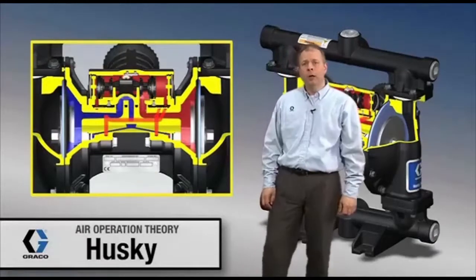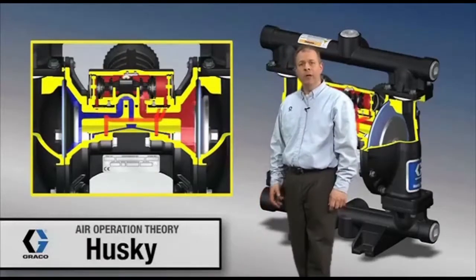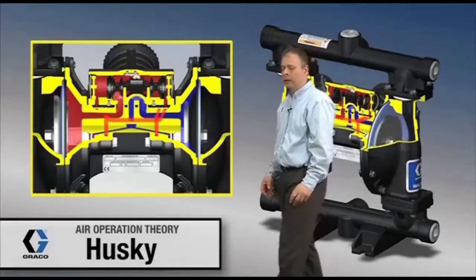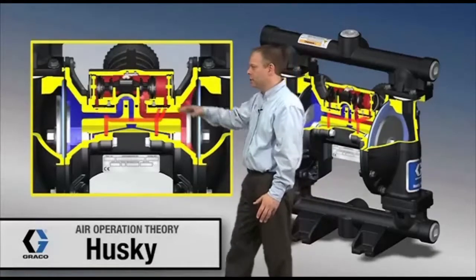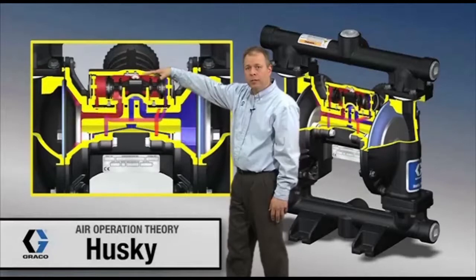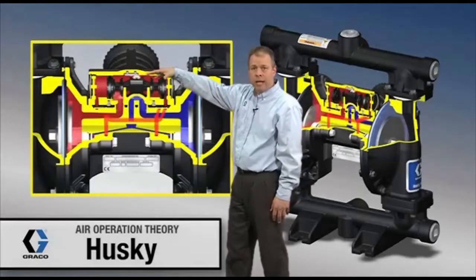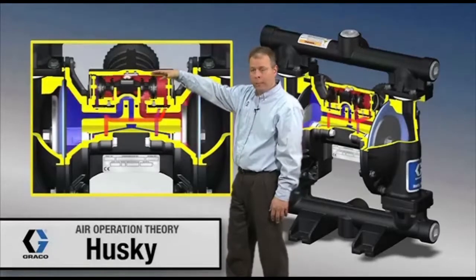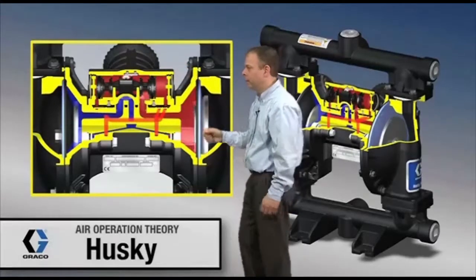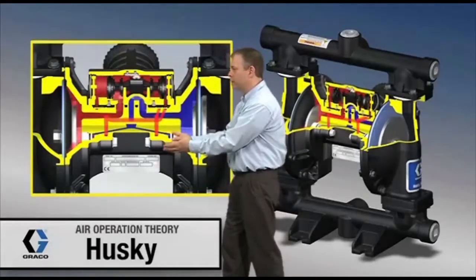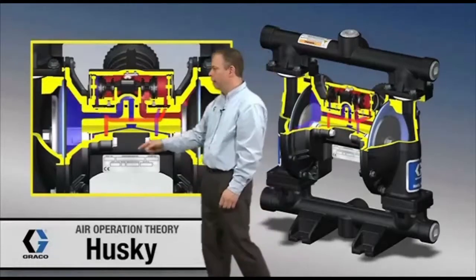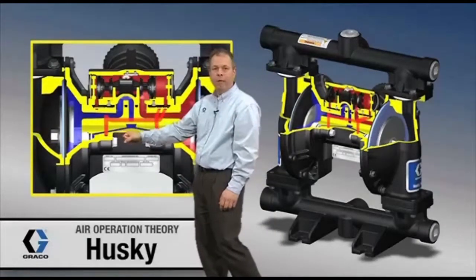We're going to talk about the air valve and air logic in the Husky 1050 pump. Component identification: the air valve is on top with four bolts — it's a modular design, so if you need to replace or repair it, four bolts and it pops right off. Behind the first diaphragm there's a poppet valve, and on the other side, another poppet valve.